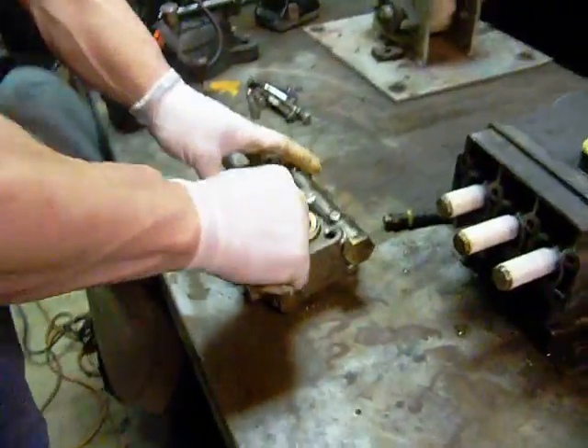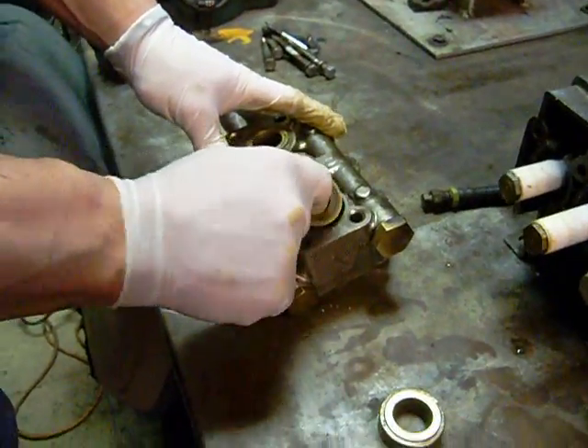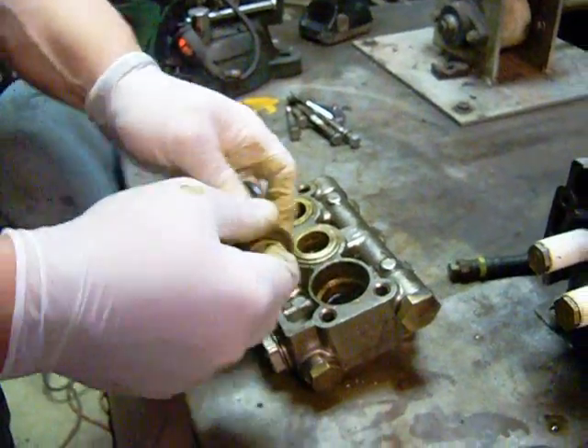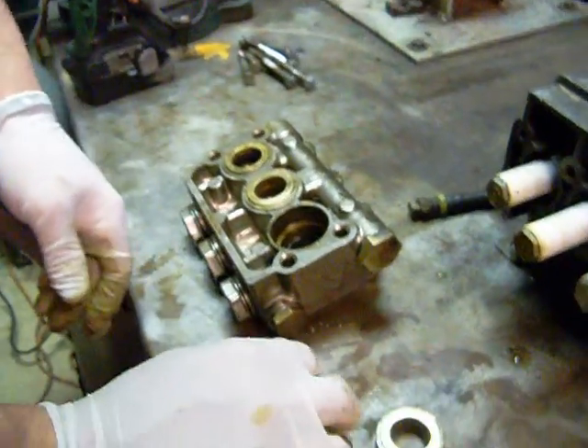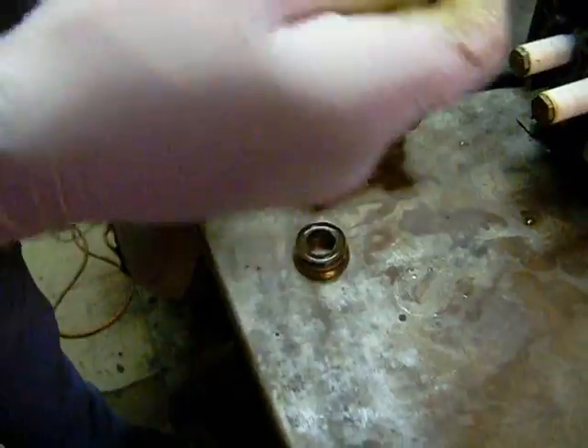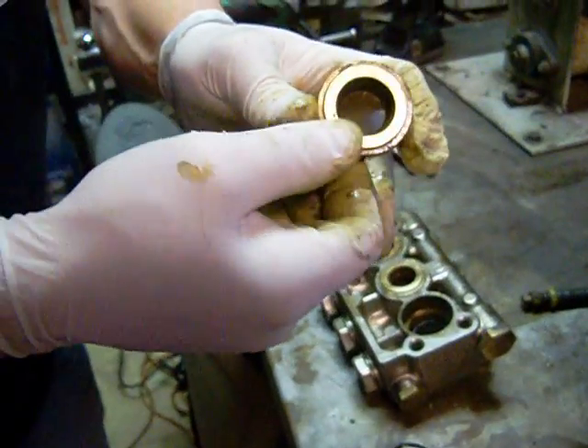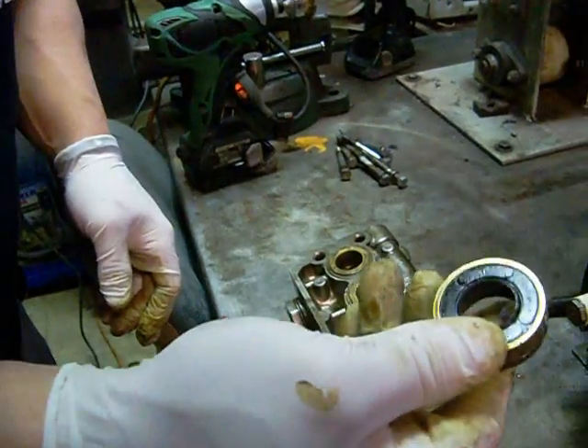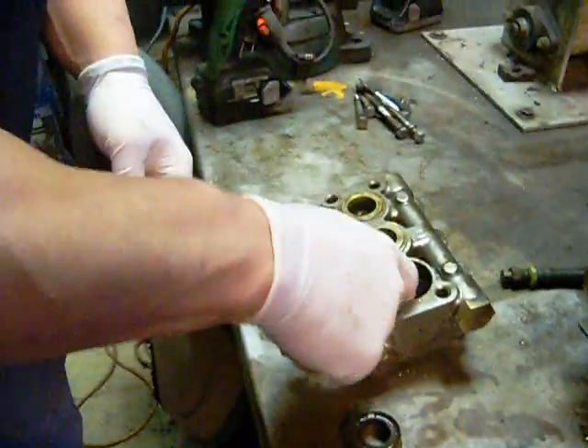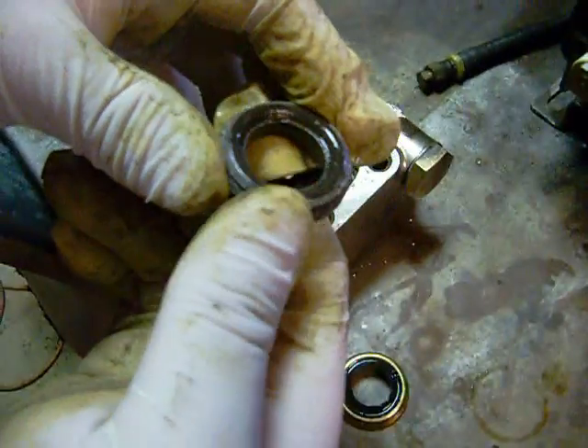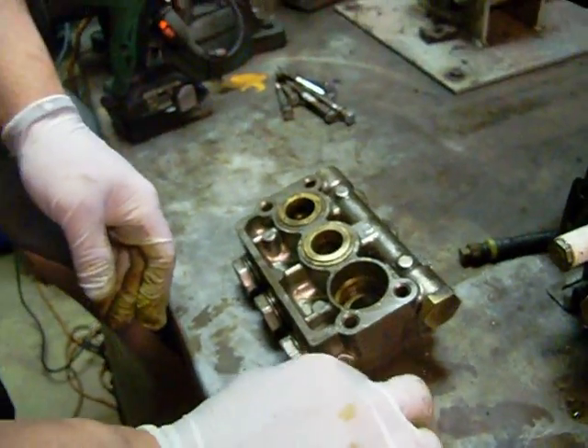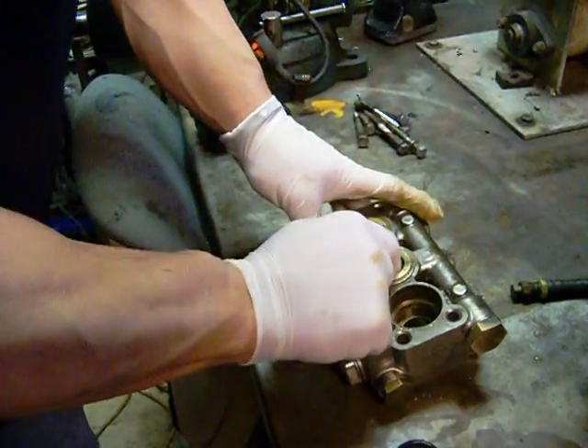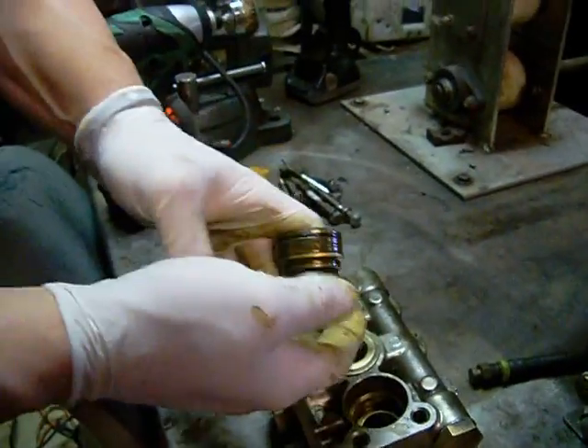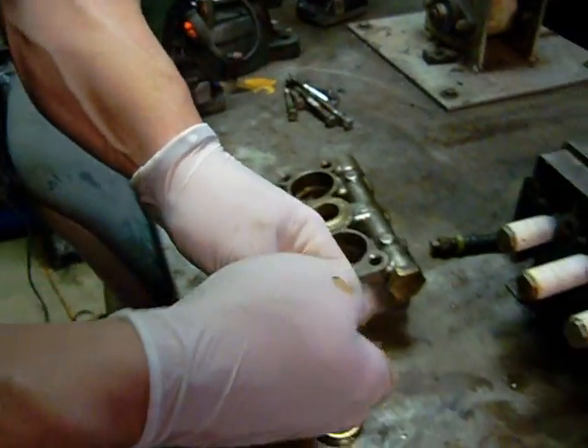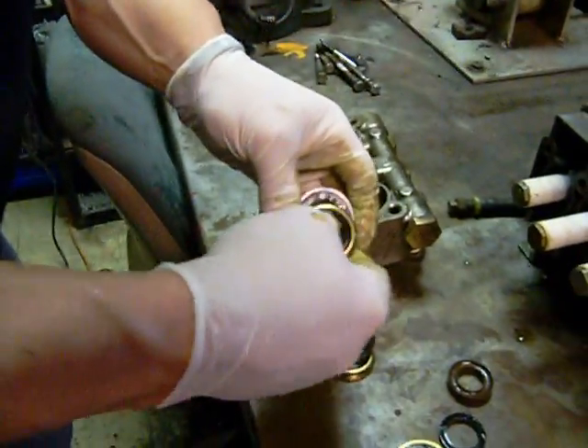This one's a little loose because I already loosened it. Alright, everything came right out — that's very good, this is what you hope will happen. The first piece you see that is brass contains your low pressure seal. Your high pressure seal is farther down in the pump — that would be brown. You see how torn up these are. What we're going to do is try another one. Oh, got lucky again — sometimes these are really hard to remove.